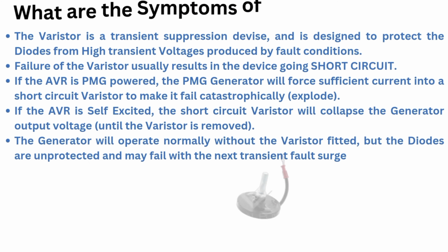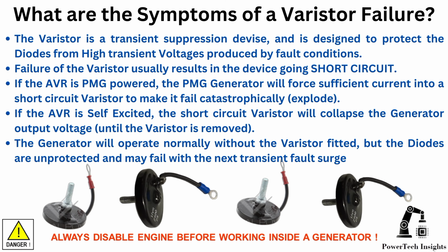Fault finding, testing of a varistor. Possible symptoms of a varistor failure. The varistor is a transient suppression device and is designed to protect the diodes from high transient voltages produced by fault conditions. Failure of the varistor usually results in the device going short circuit. If the AVR is PMG powered, the PMG generator will force sufficient current into a short circuit varistor to make it fail catastrophically, explode. If the AVR is self-excited, the short circuit varistor will collapse the generator output voltage until the varistor is removed. The generator will operate normally without the varistor fitted, but the diodes are unprotected and may fail with the next transient fault surge.